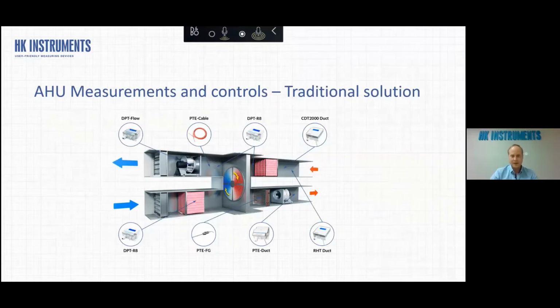So let's take a look at the air handling unit control system. This is the very basic application, maybe the most common for our products, because we can measure all the necessary parameters which have impact to the control system. So for example, if we are speaking about the pressure and the differential pressure, that's our core know-how. So basically what you need to measure from this unit with the differential pressure is the fans and the filters.